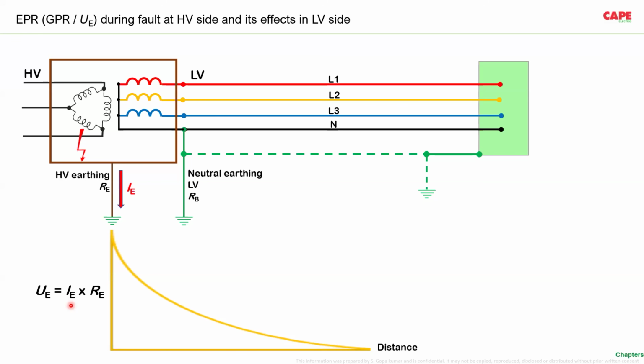Please note that in all these standards, as well as in my presentation, I will be using two or three terms. One is IF. IF is the fault current. IE is the current which is going through the earth electrode. And there is a fault current flowing through the metallic fault return path, such as the earthed conductor in an overhead line or through the shielding in an underground line. So there are different terms used. Basically, the potential gradient or the peak of the EPR is equal to the earth electrode resistance multiplied by the current which is flowing through.